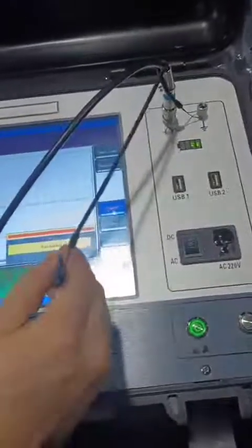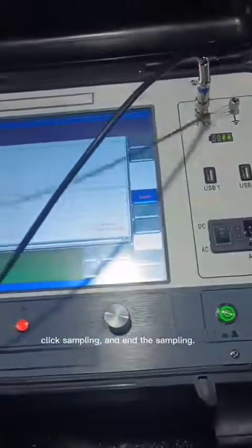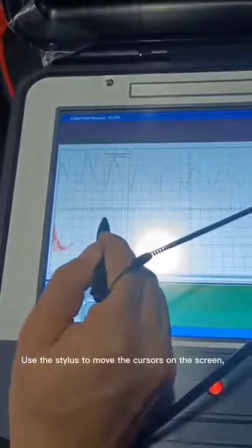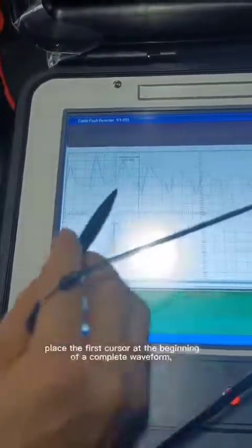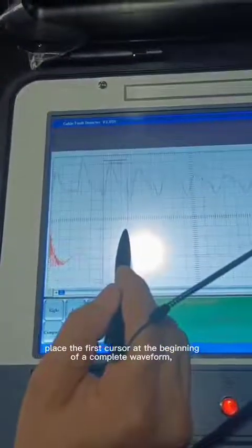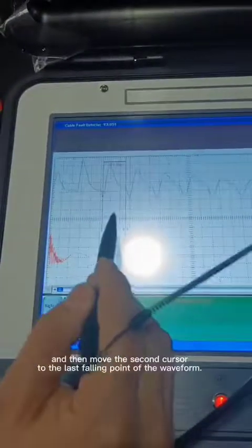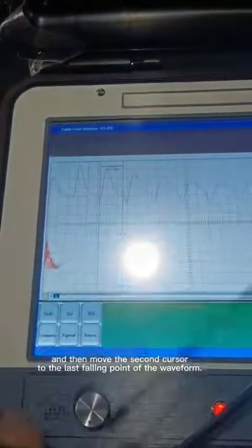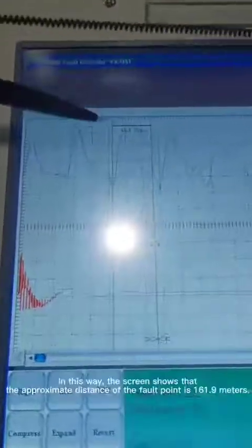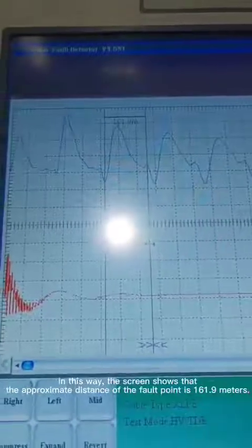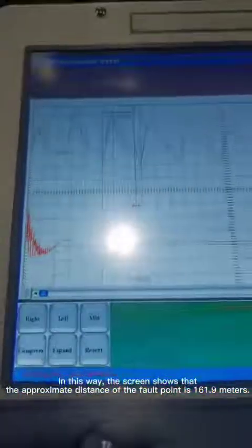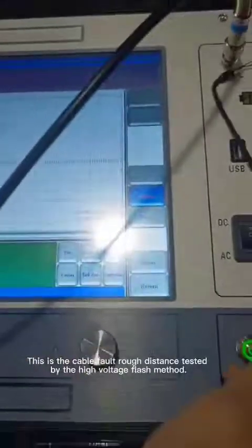Now we can intercept the waveform. Click Sampling and end the sampling. Use the stylus to move the cursors on the screen. Place the first cursor at the beginning of a complete waveform, and then move the second cursor to the last falling point of the waveform. In this way, the screen shows that the approximate distance of the fault point is 161.9 meters. This is the cable fault rough distance tested by the high voltage flash method.